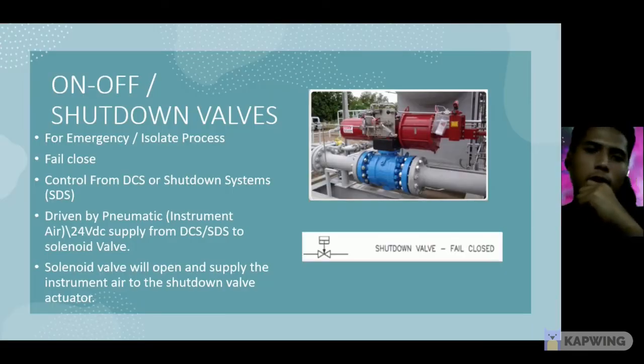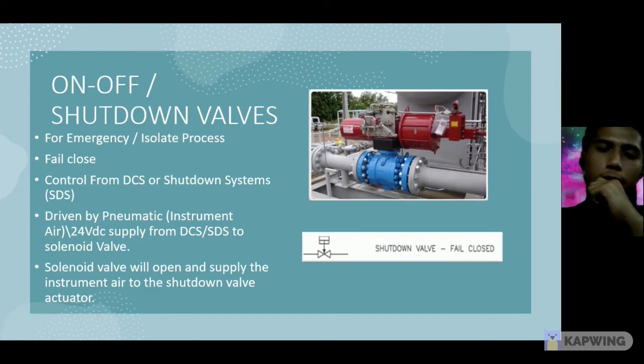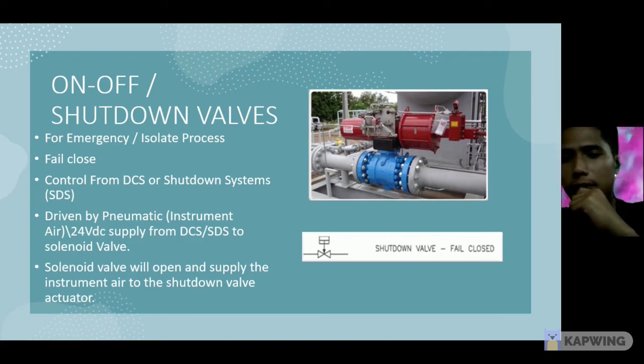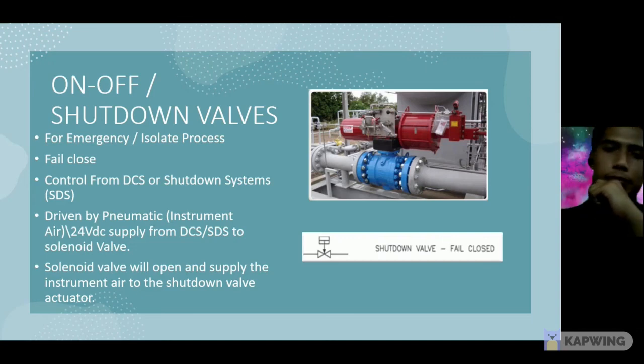Alright. Next is the on, off, or shutdown valve. It is used for emergency or to isolate the process. Each type is fail close. Controlled by the shutdown system. Driven by pneumatic, so the valve will open and supply instrument air to the shutdown valve actuator. The right side diagram shows the valve and the piping, and the lower part of the diagram is the sketch diagram for the shutdown valve.